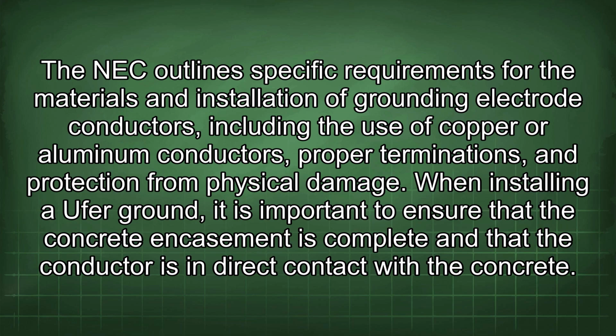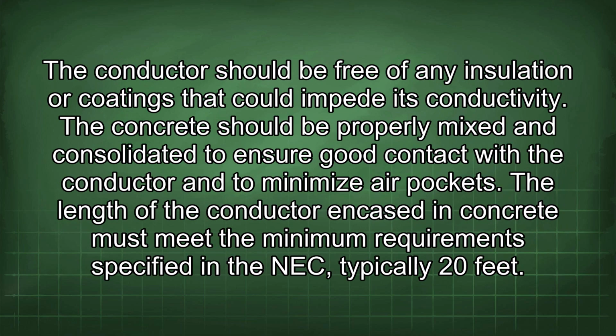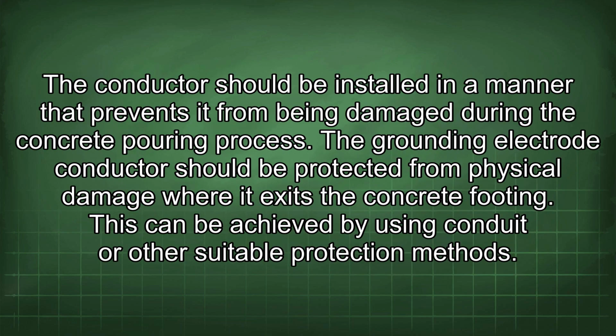When installing a Ufer ground, it is important to ensure that the concrete encasement is complete and that the conductor is in direct contact with the concrete. The conductor should be free of any insulation or coatings that could impede its conductivity. The concrete should be properly mixed and consolidated to ensure good contact with the conductor and to minimize air pockets. The length of the conductor encased in concrete must meet the minimum requirements specified in the NEC, typically 20 feet. The conductor should be installed in a manner that prevents it from being damaged during the concrete pouring process.